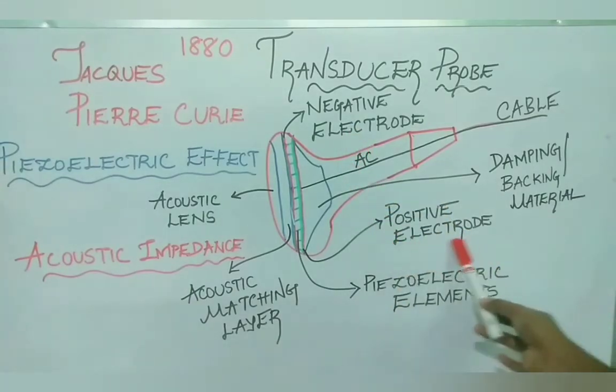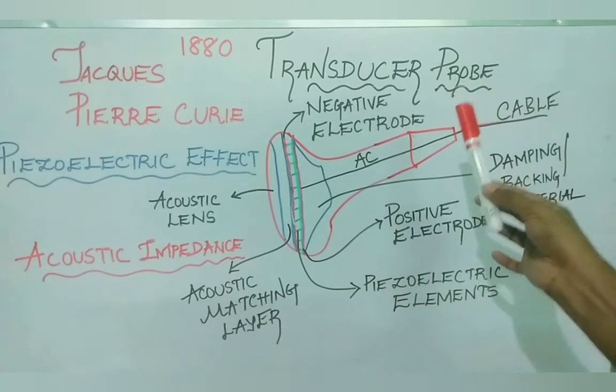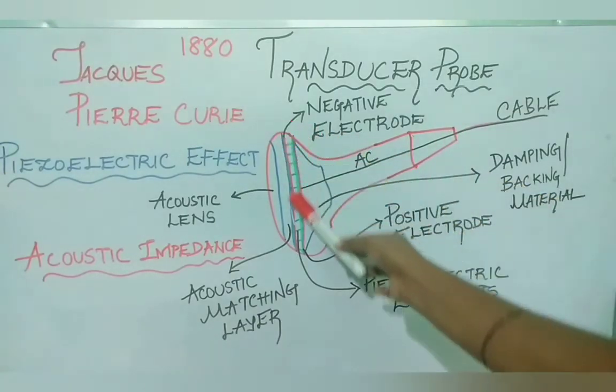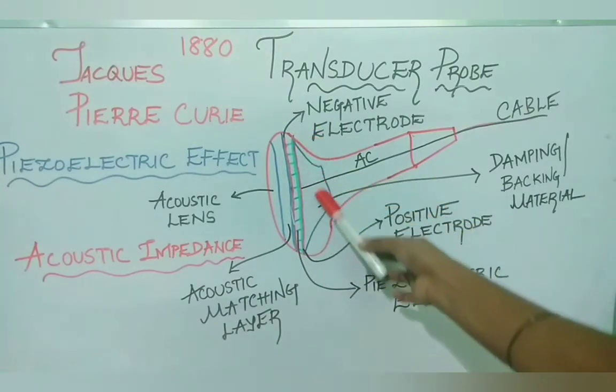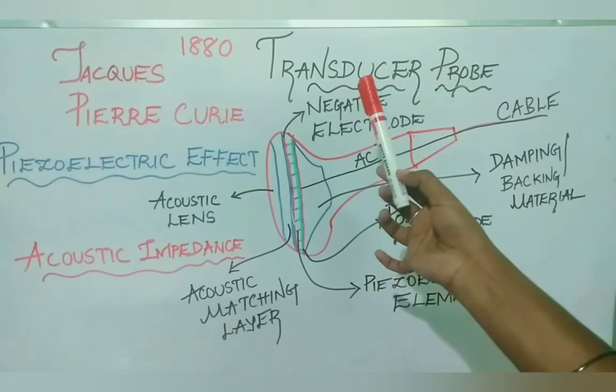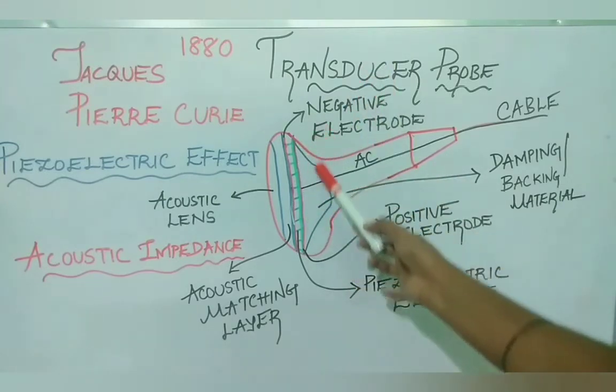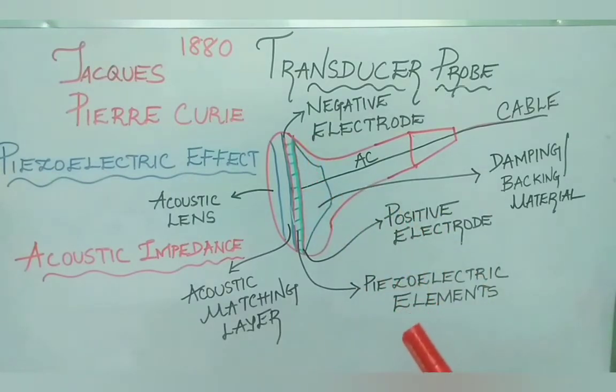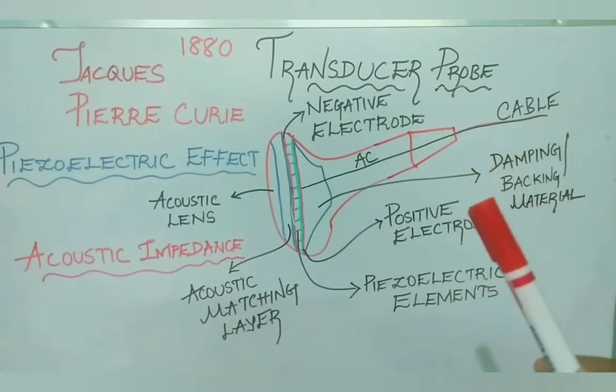Negative as well as positive electrodes are for electrical connection. Damping material is adhered to the back of the piezoelectric elements or crystals, behind the positive electrode. It is made up of plastic or epoxy resin mixed with tungsten filaments. The role of damping or backing material is to limit the duration of vibration of piezoelectric crystals or elements.